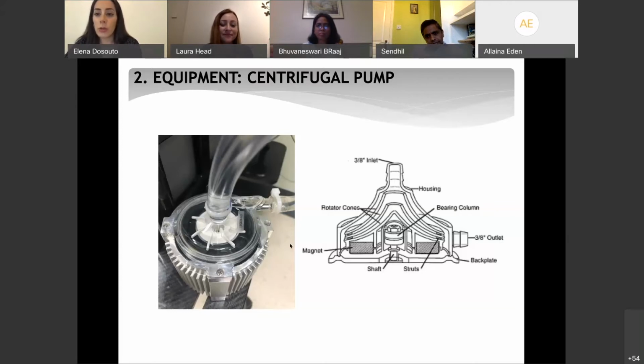They cannot overpressurize, which is good, but as I mentioned earlier, they can generate a huge amount of negative pressure if this is spinning. So if for some reason your line here is clamped, it's going to create loads of negative pressure because it's going to try and suck that blood there.